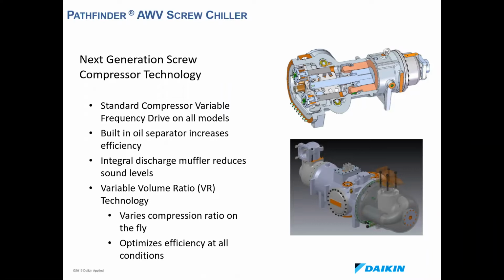So on VVR, what that's really doing for you is it's going to be varying your compression ratio and your volume ratio on the fly, so that you can optimize your operation at any given condition when your ambient temperature or your leaving water temperature are changing.